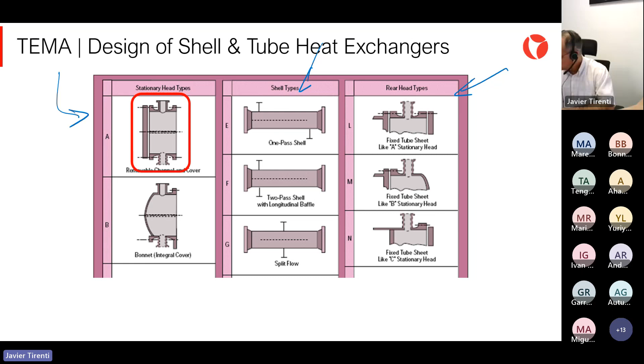So how does this designation work? Well, the designation is very straightforward. Depending on the operating, maintenance, and design requirements, the designer is going to select one alternative or another in terms of the three different groups that we are seeing on the screen. For example, if the selection is made for stationary head type A, shell type E, and rear head type M, we are going to arrive at a shell and tube heat exchanger that is AEM, and that has obviously different connotations.